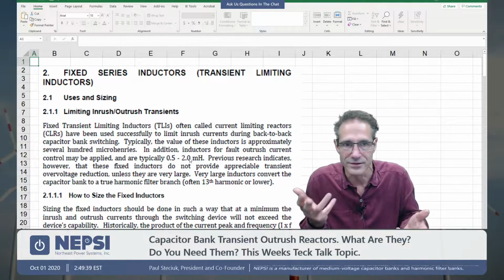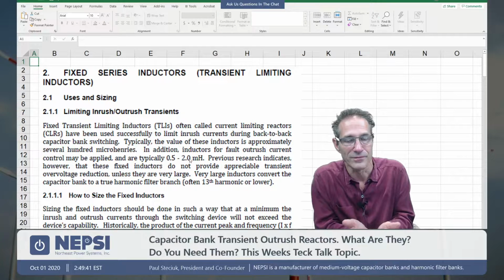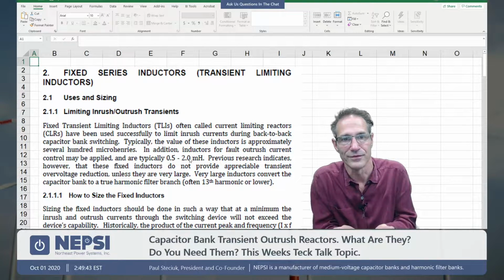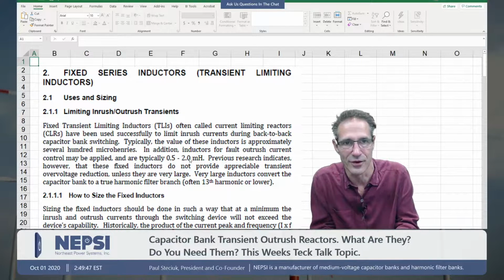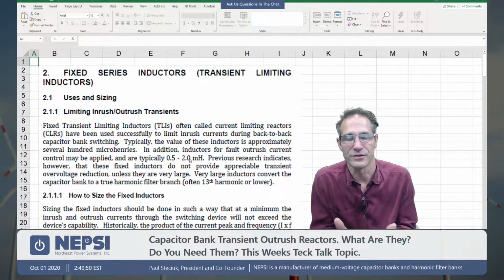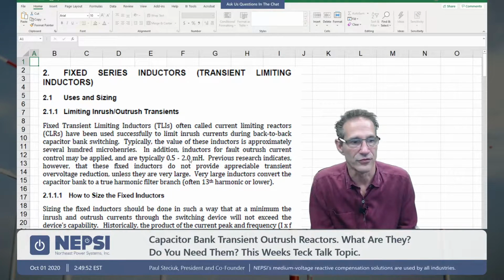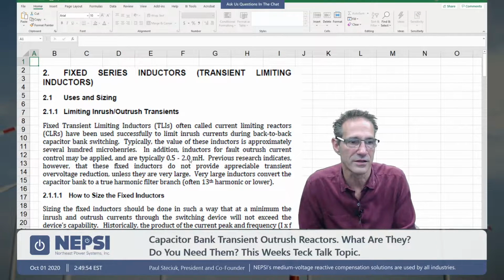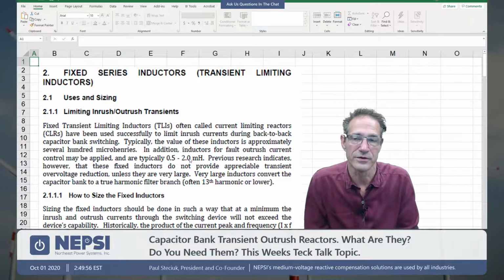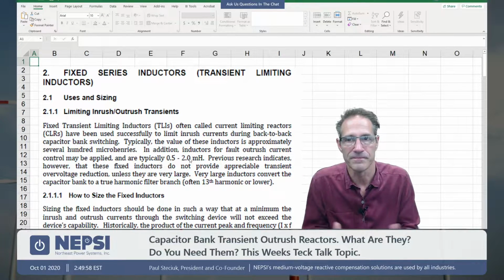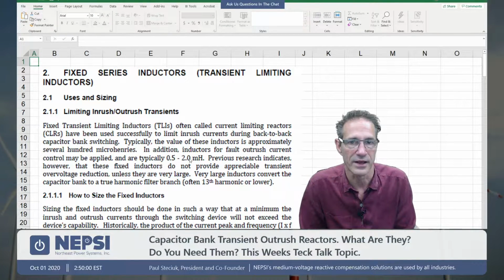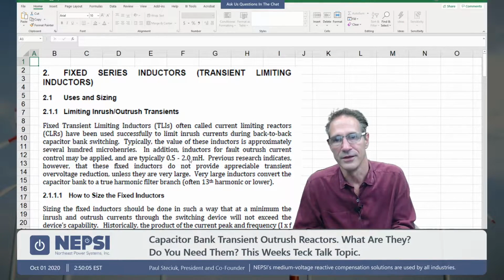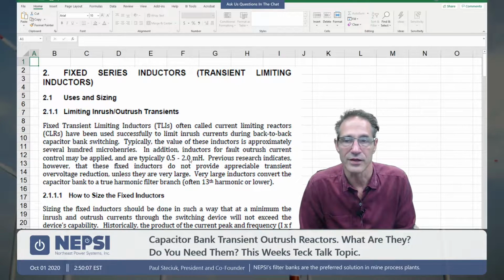And just common sense says, hey, if I've got only a surge capacitor, do I really need to put an outrush reactor associated with it? And common sense says no. So that's what the standard speaks to. But if you strictly follow C37.06, it would say, yeah, you need to put outrush reactors in there. So you have to kind of put on your design hat and decide what's necessary for the project. But I can tell you, with surge caps, you would not typically see an outrush reactor. For a very large cap bank, you would.